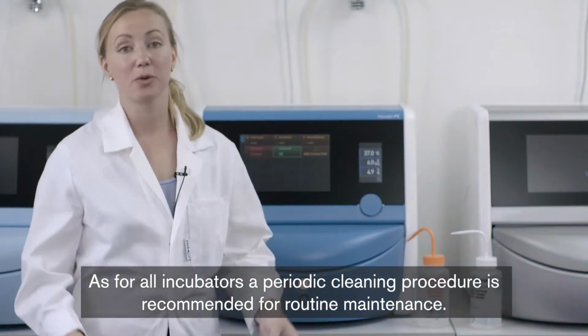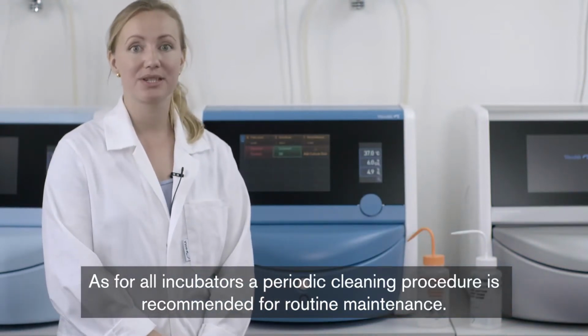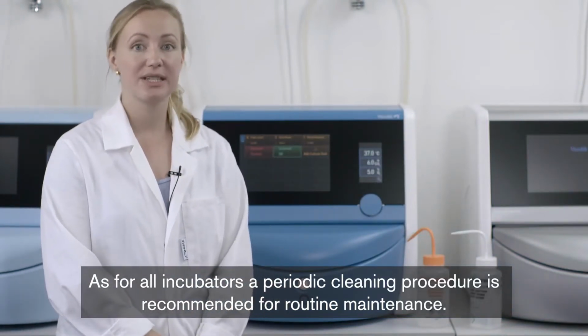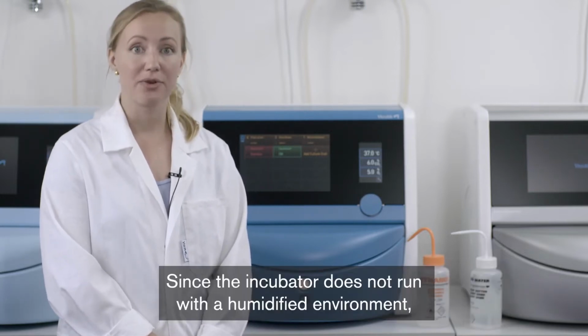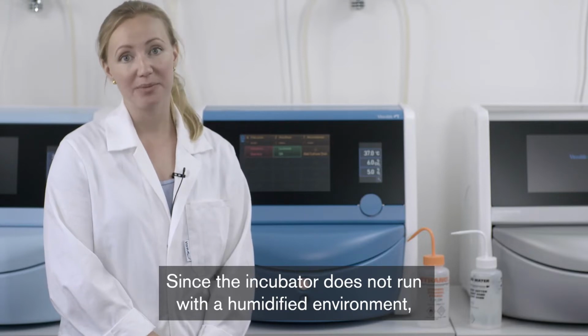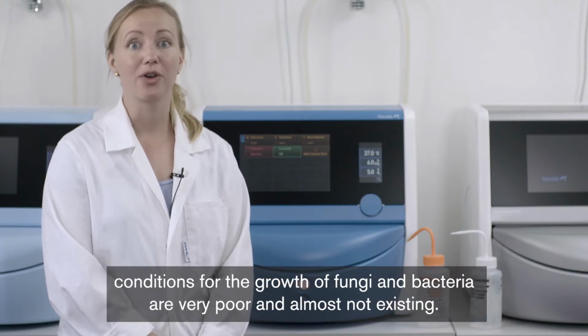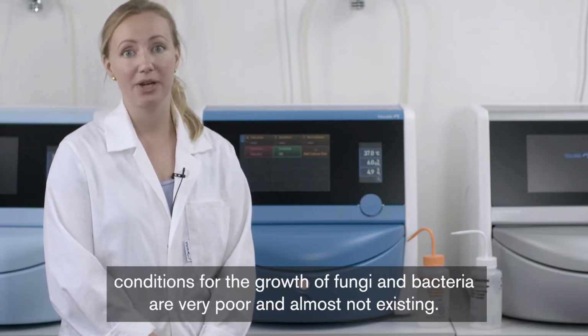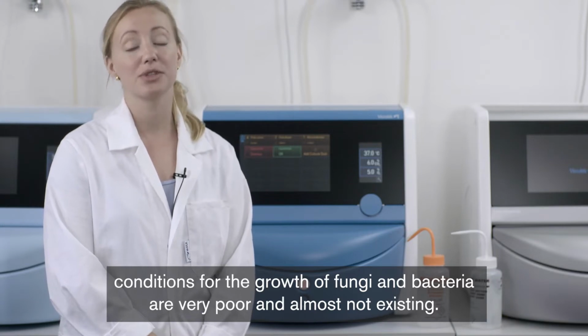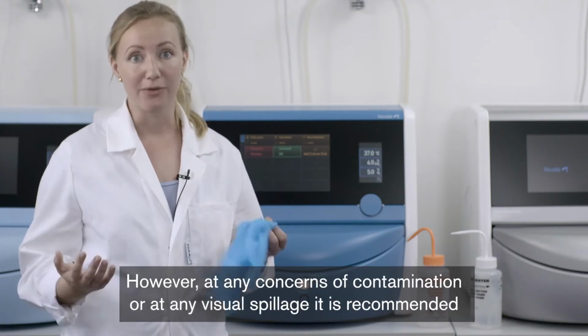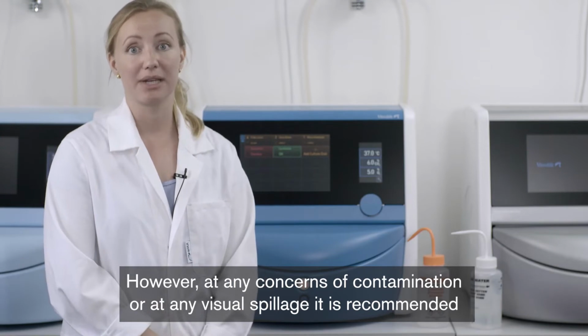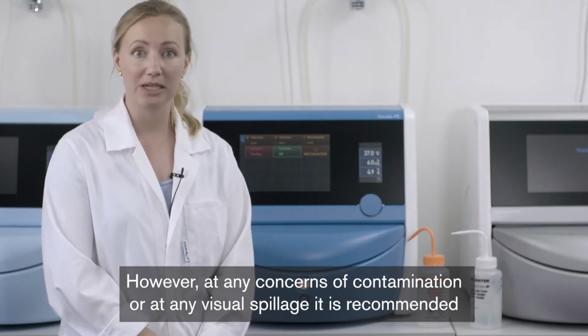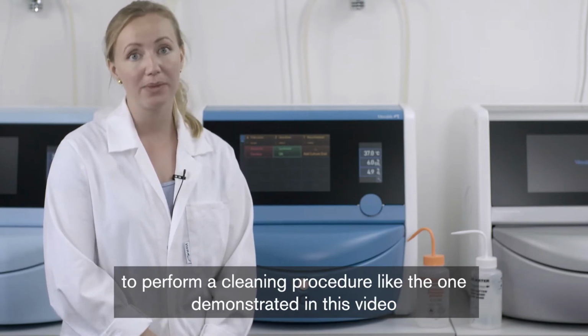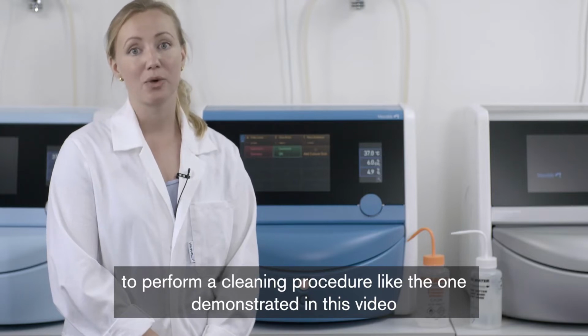As for all incubators, a periodic cleaning procedure is recommended for routine maintenance. Since the incubator does not run with a humidified environment, conditions for growth of fungi and bacteria are very poor and almost non-existent. However, at any concerns of contamination or any visual spillage, it is recommended to perform a cleaning procedure like the one demonstrated in this video.